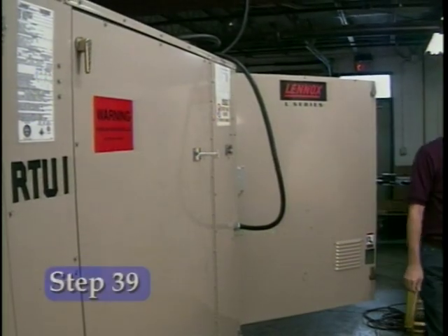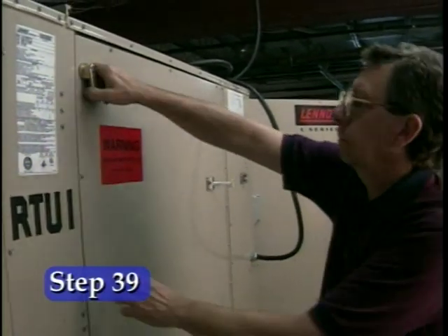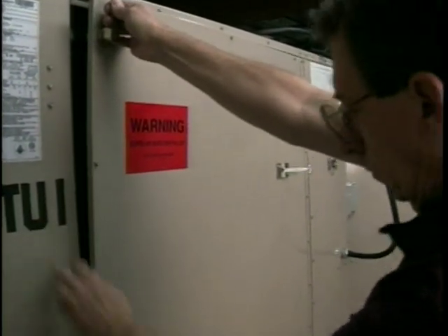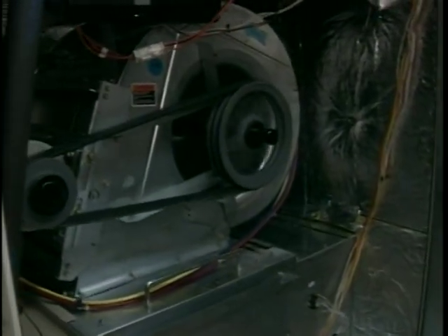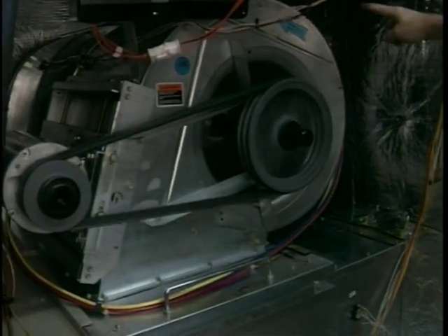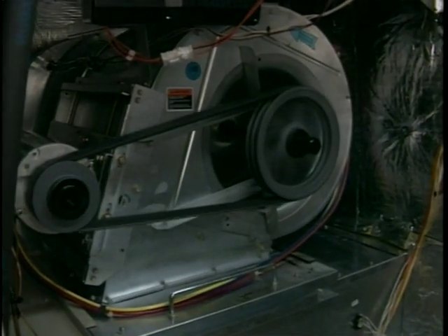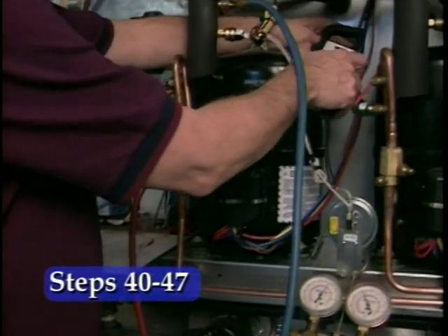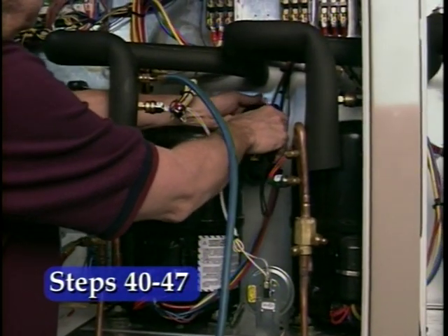Verify correct indoor blower rotation. You must correct rotation if necessary before proceeding. If rotation must be corrected, do it at the main disconnect only. Do not change any wiring on the system contactors. Take amperage and pressure readings of each compressor.